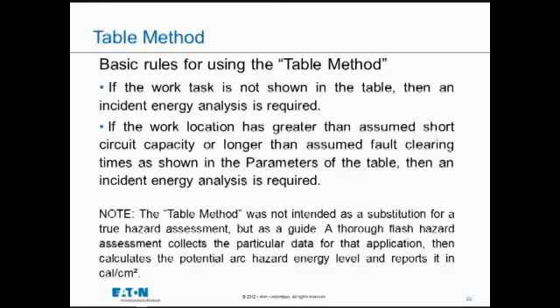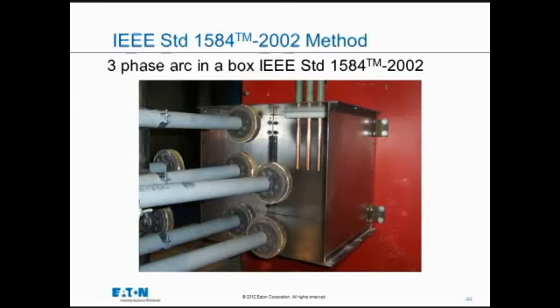What the best practice guide is hoping people will do is use formulas and equations that were developed to use a calculation rather than the table method. And this slide is just showing what's called the arc in a box experiment that was done back in the year 2002 to determine arc flash energies coming from arcs off of a 3-phase system. So the round discs on the white tubes are calorimeters. They're measuring energy. And then inside that steel box, it may be difficult to see from the back, are 3 copper-clad steel conductors, and they would develop a 3-phase arc on those conductors at the tips and measure how much energy is coming from there. And that experiment was done about 300 times and came up with equations that are used now in the software for calculating arc flash hazard. It is the preferred method on both sides of the border based on the Z462 standard and the NFPA 70E standard, with the table method being the backup method, alternative.